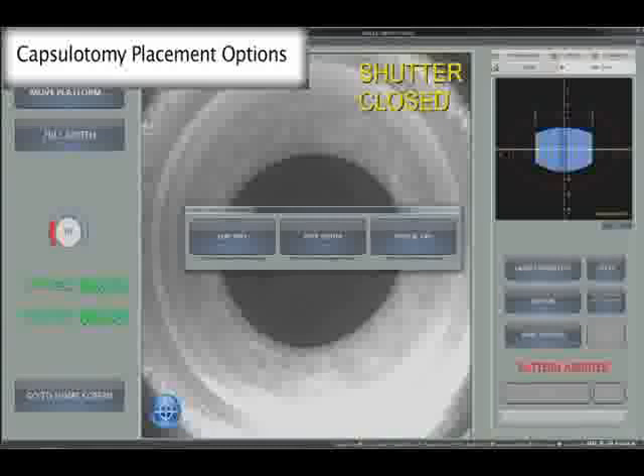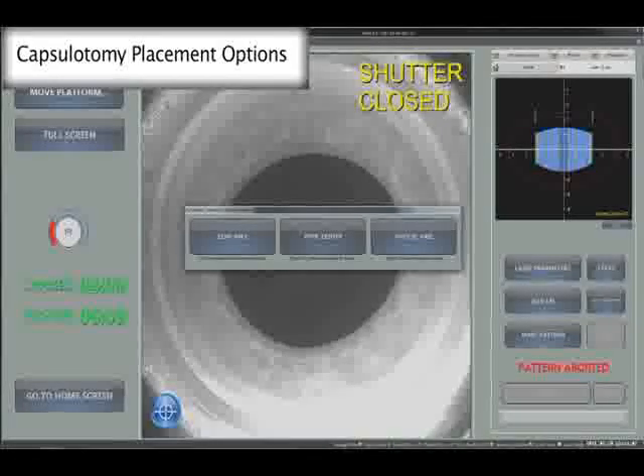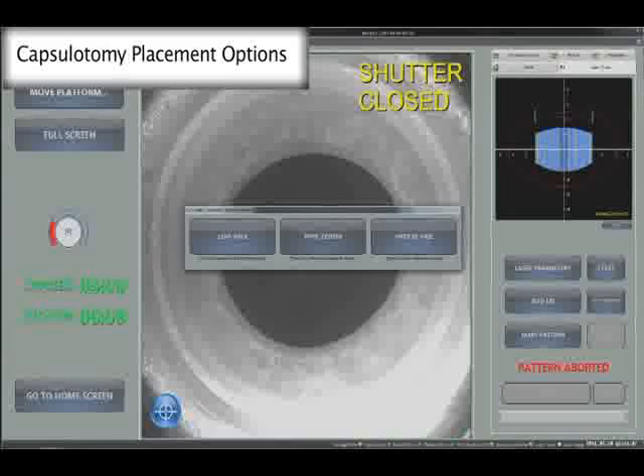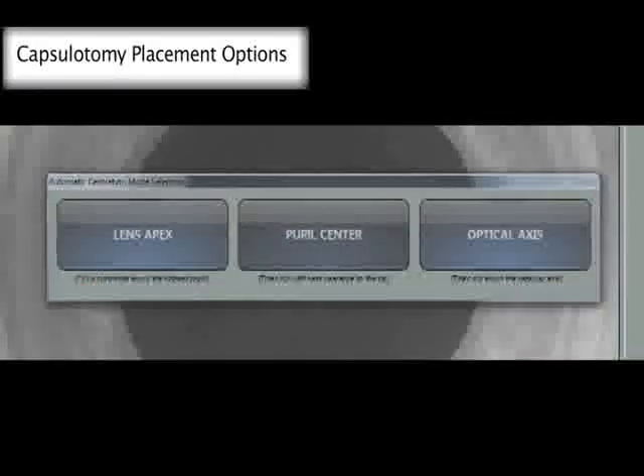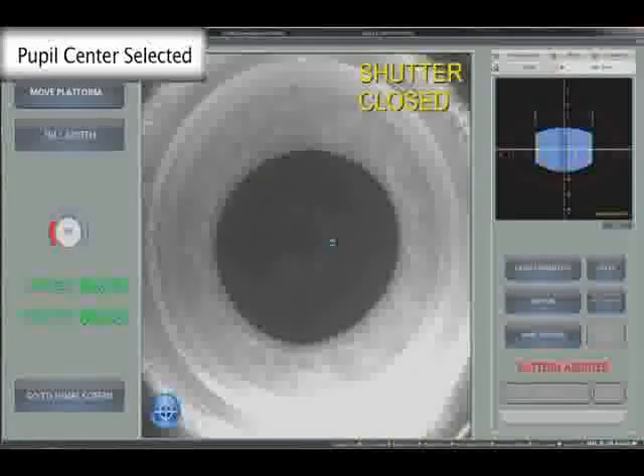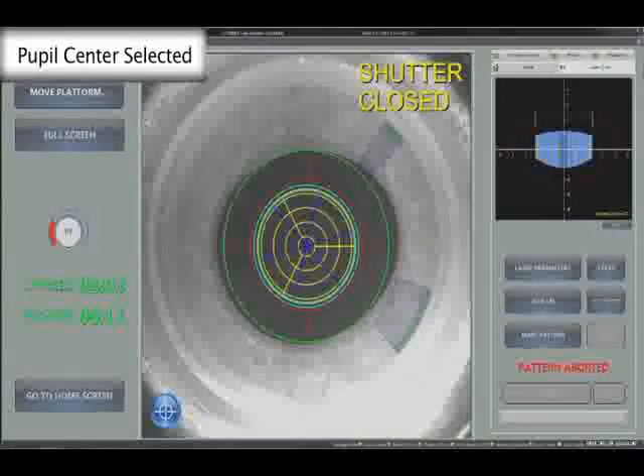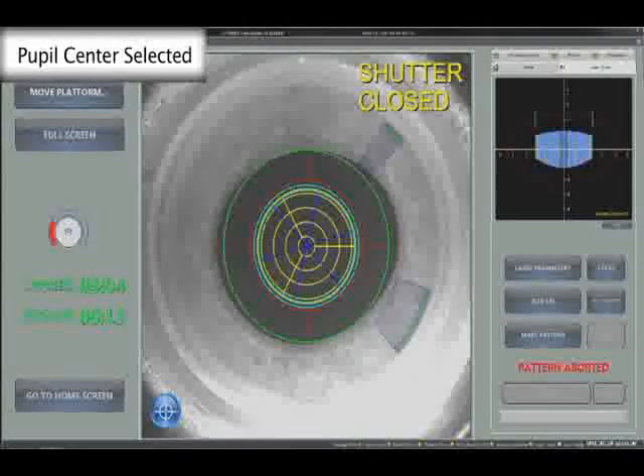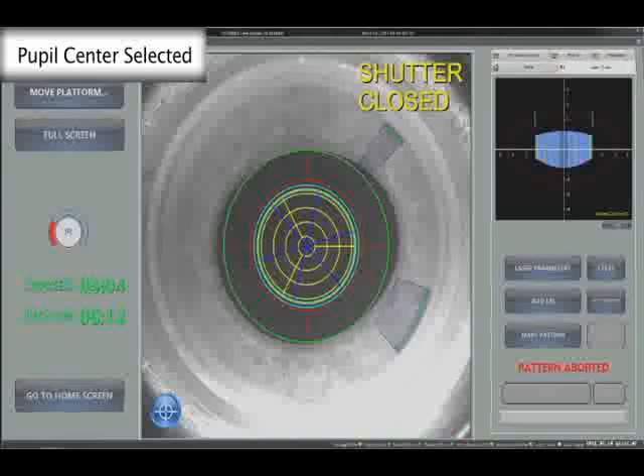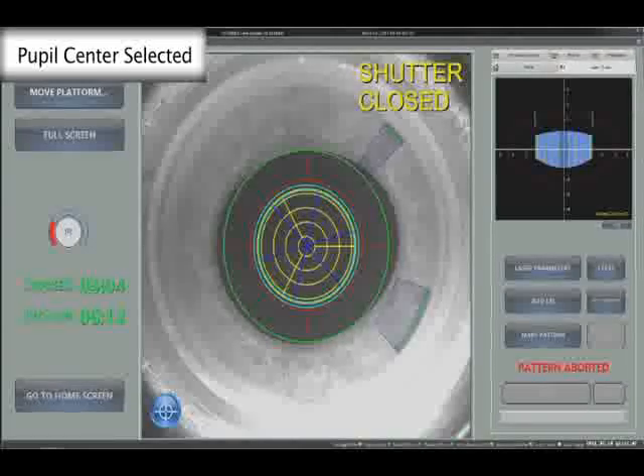When planning the treatment after the image is complete, the surgeon has the option of placing the capsulotomy over the centre of the pupil, over the anterior apex of the lens, or over the optical axis of the lens. The planning screen then shows the diameter of the short axis of the pupil in green, the chosen capsulotomy diameter in red, and the selected fragmentation pattern in blue and yellow.